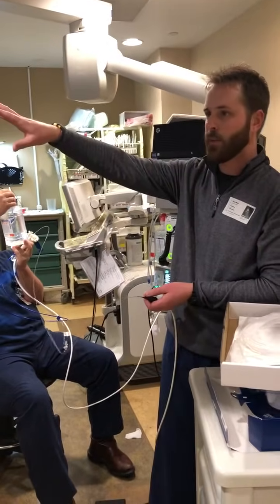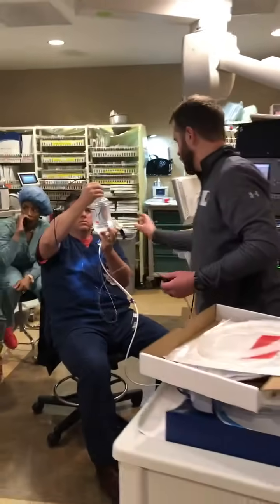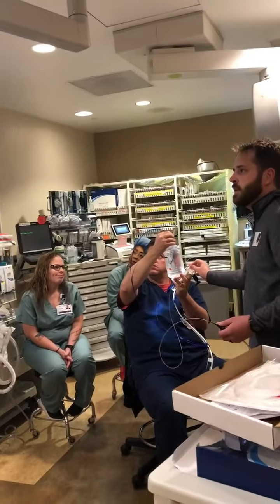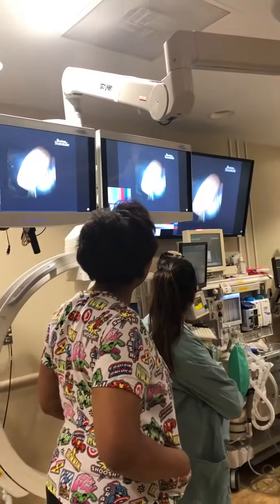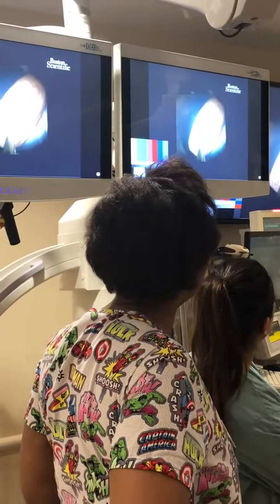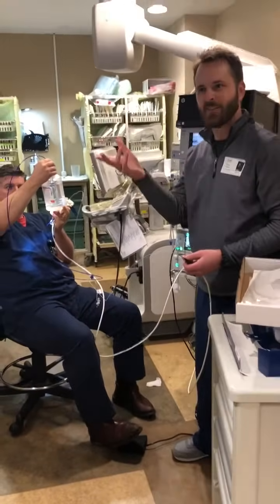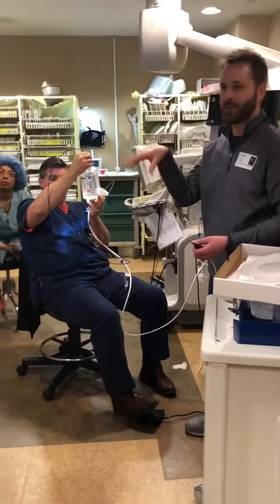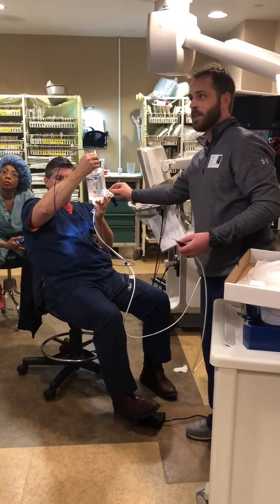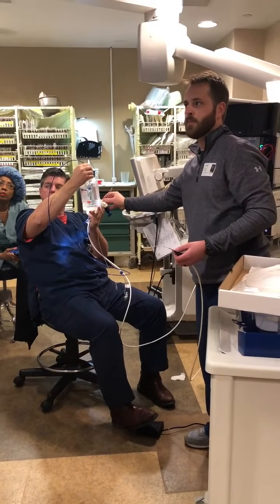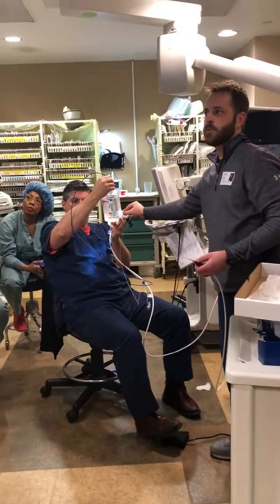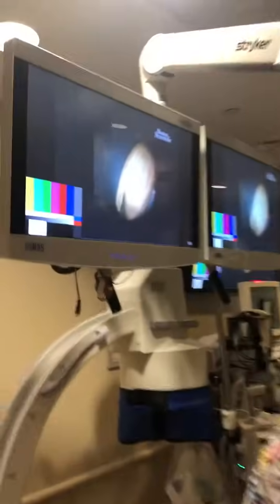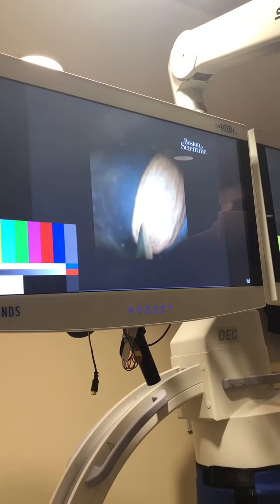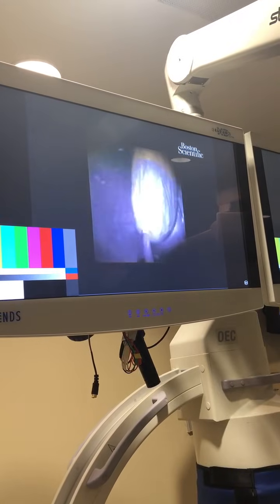So let's act like this almond is our stone. Okay. So what I'm going to do is I'm going to push the probe out. See that? I'm going to push it out and touch the stone. And I'm going to back up a little bit and then we'll activate. If you notice, you lose, just for a second, you get kind of like a flicker. That's totally normal. It's just that energy transferring back through there. Okay. And then, just to give you real life, you see the metal tip of the probe? That's what's creating the bubble. Okay. So we're going to get that close, touch it, back off, create a little bit of space, and then activate, activate, activate, and we're just going to keep blasting.